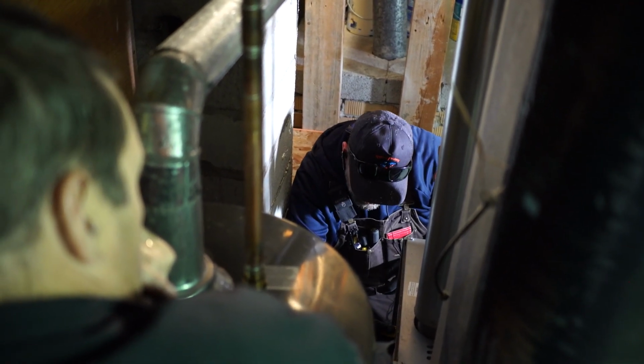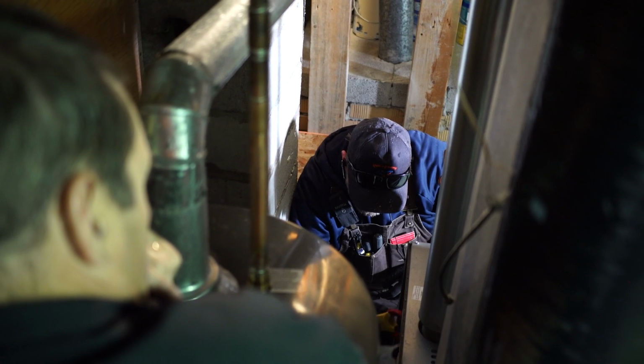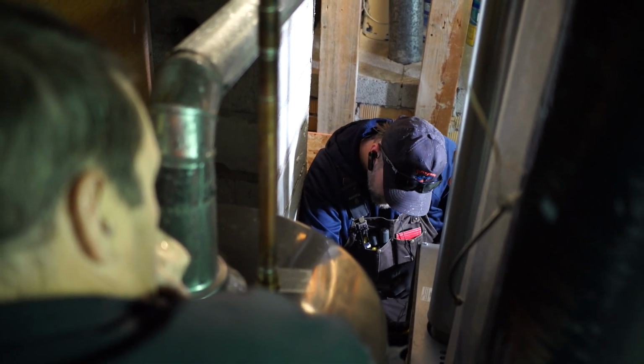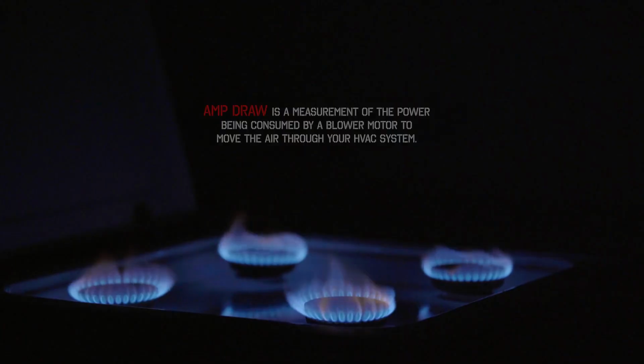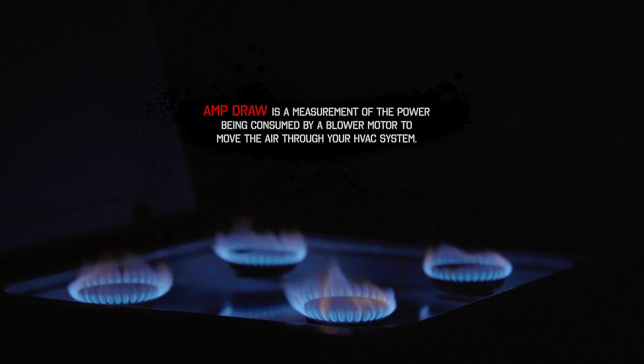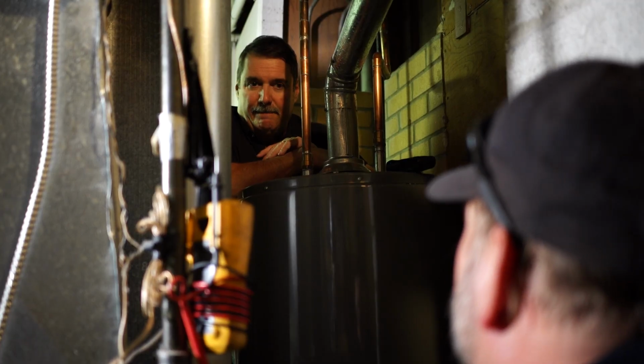While our inducer's running, I'm checking my amperage draw on the inducer motor—1.0. Now the amperage draw on the motor is written on the side; it says 1.71 amps.